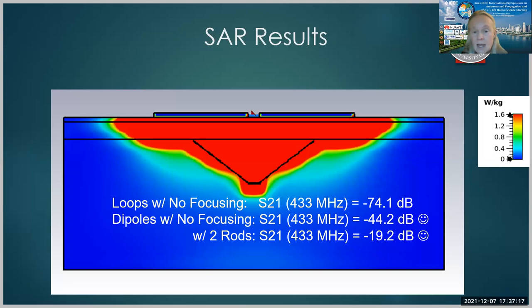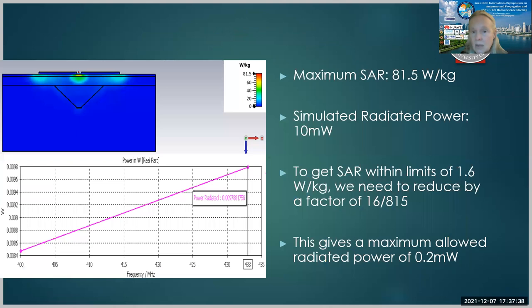So we went from dipoles with no focusing, having an S21 of minus 44 decibels to dipoles with two rods having an S21 of minus 19.2 decibels. This is a substantial improvement and both of these are better than our loop case. So again, we have a maximum SAR in this case of 81.5 and we need to divide that down. So we end up with a total maximum allowed radiated power in this case of about 0.2 milliwatts.